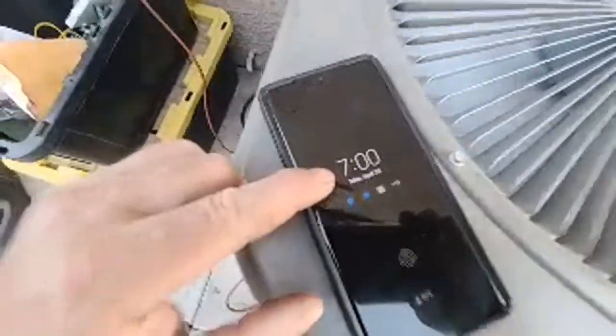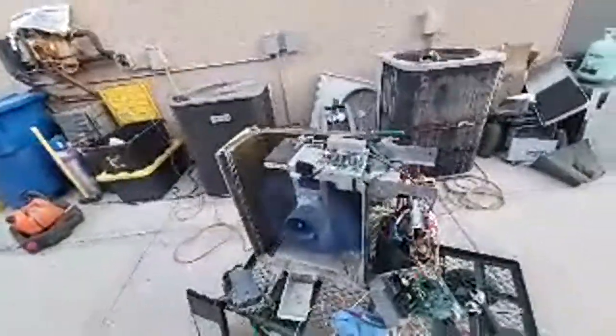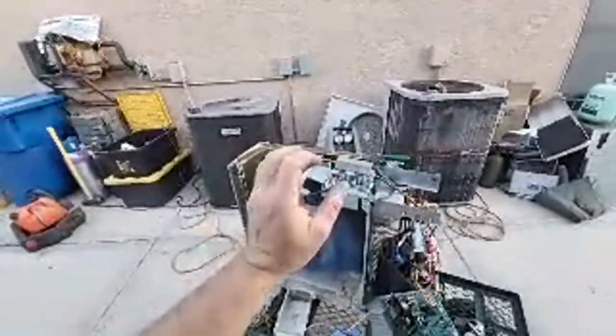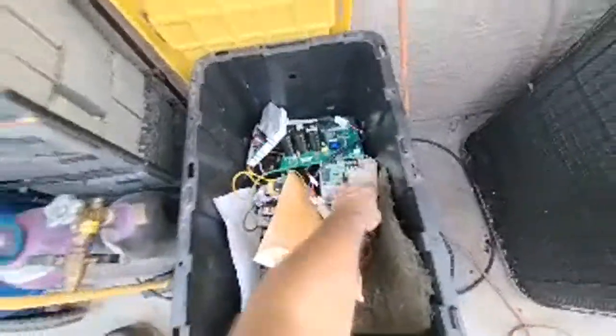Yep, 7 o'clock, so it dropped temperature from our time of peak use is over, so it went to second stage. So what was going on is it's the inrush discharging the capacitors and somehow shorting through something. So I think if I just hook that up to an external rectifier and not using the one in the VFD, because it blew up. Somehow it blew up this VFD's rectifier. This VFD doesn't power up at all no more.